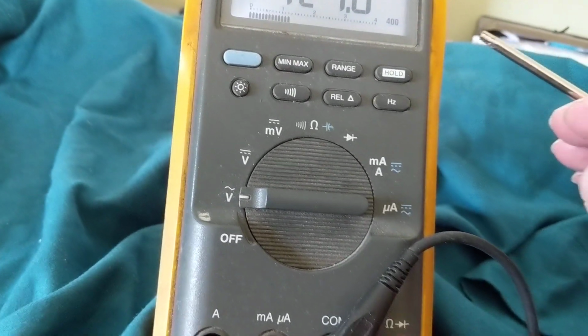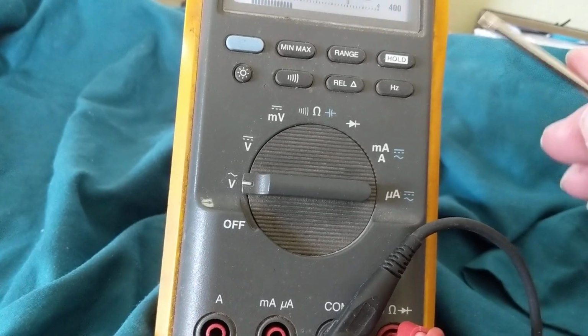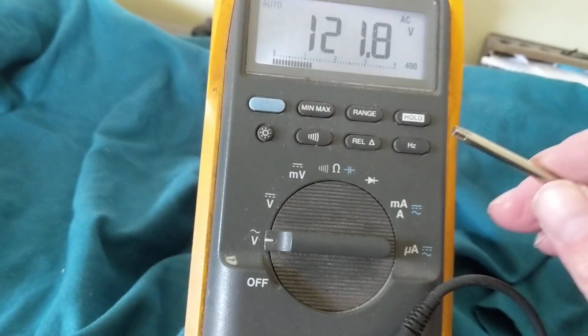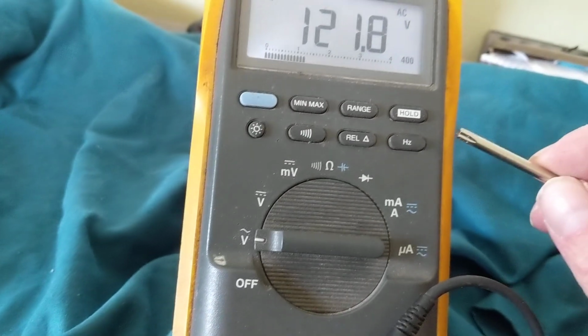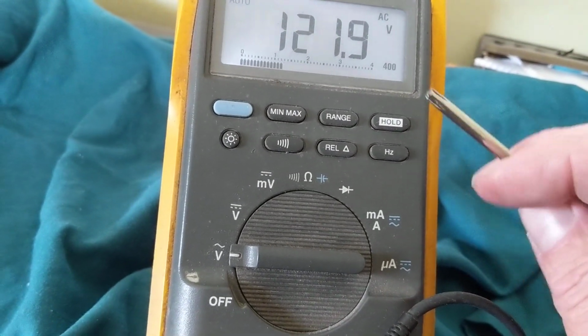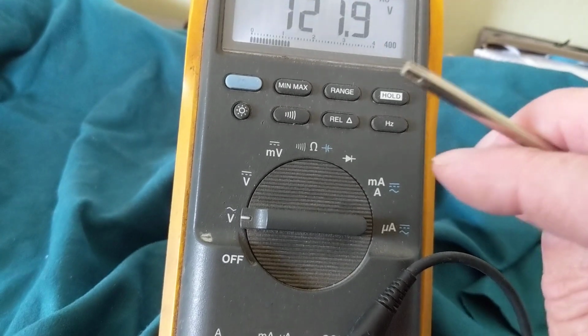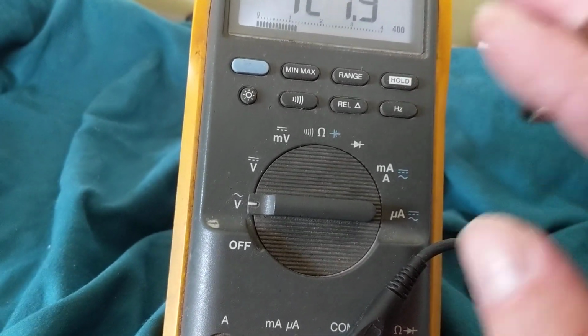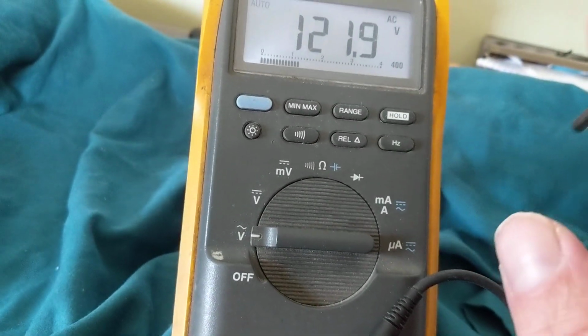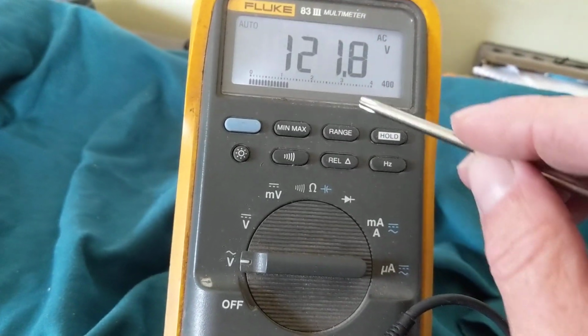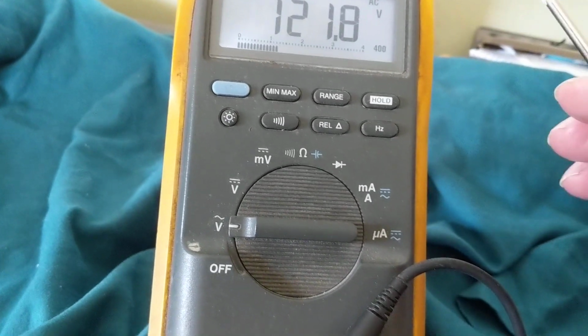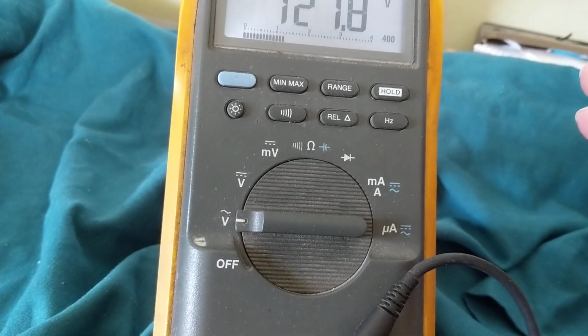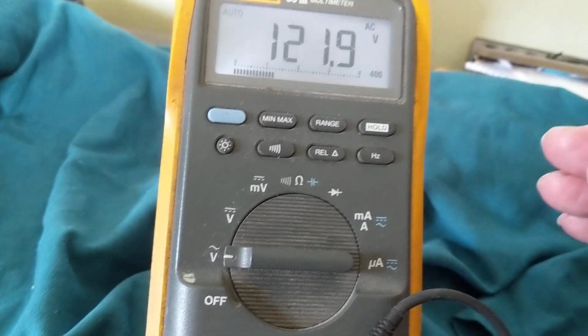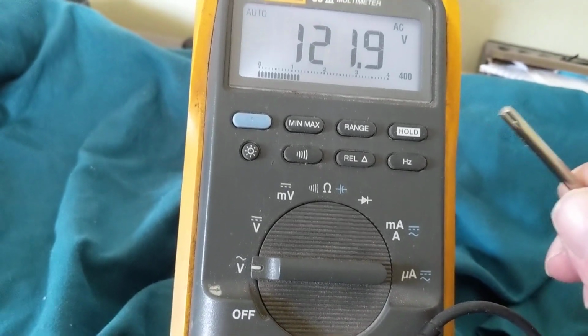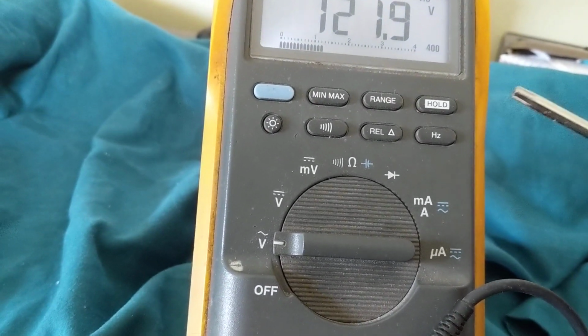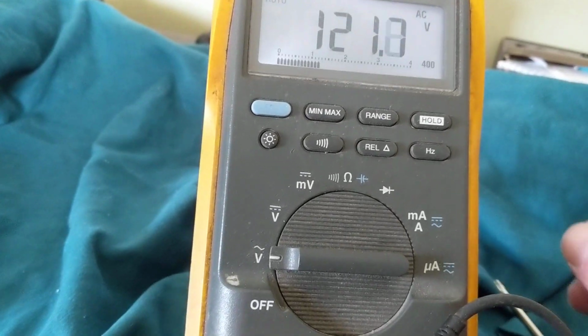Let's say there was a blackout in your house, and the power came back on. I go to the outlet after resetting the circuit breaker and measure the AC voltage. This is RMS, not peak to peak, not average, that's a different topic. We measure 121 volts from the outlet, meaning power is back on. But what other function do I have to test to make sure the outlet is working correctly? Take a guess.